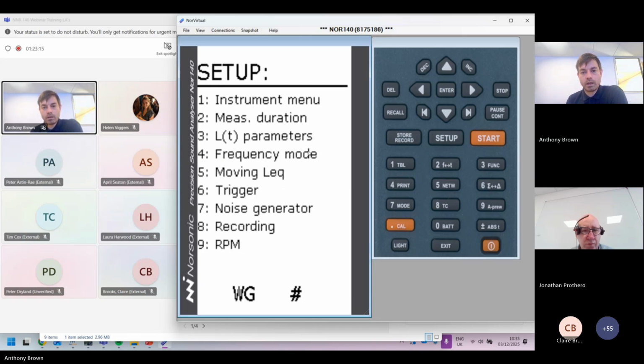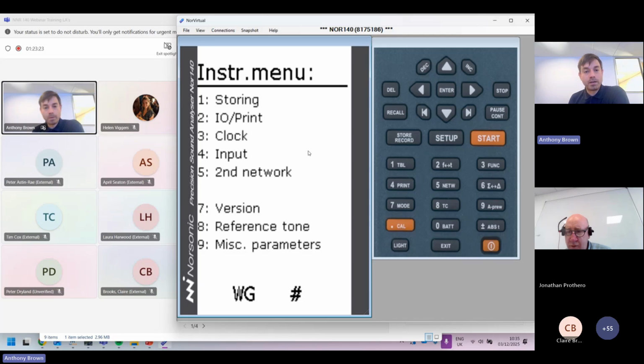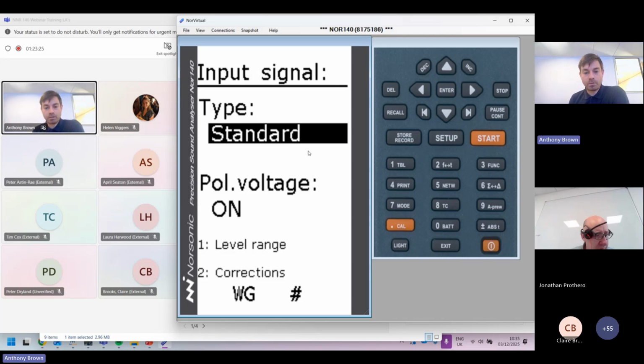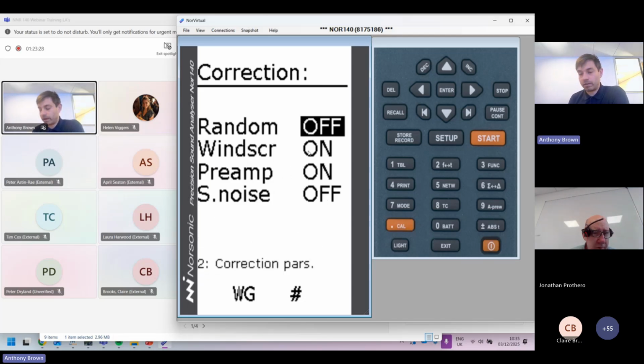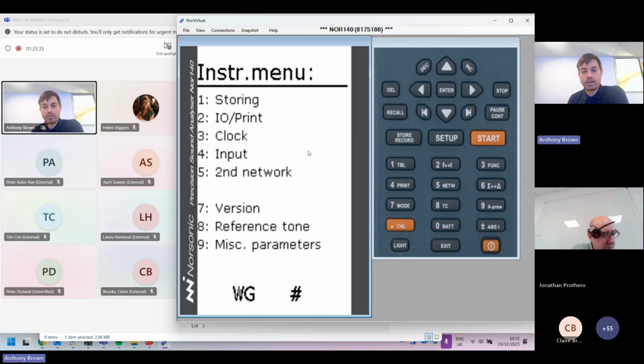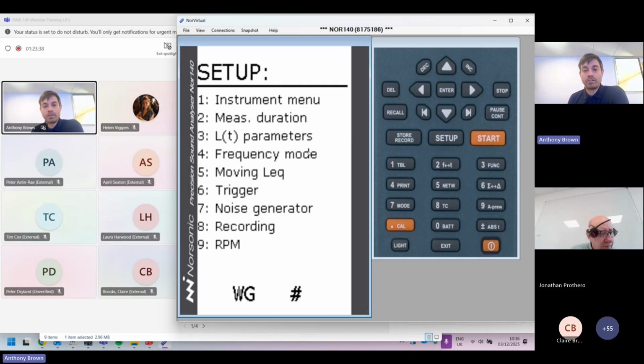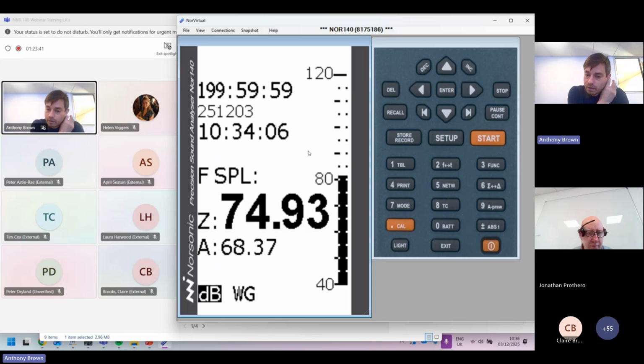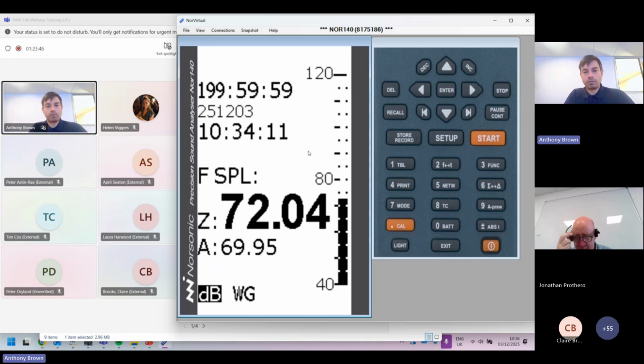So it's the enter key to go all the way back. If you are still a little bit unsure where you were with that, it's the instrument menu number 1, the input menu number 4, pressing button number 2 at the bottom for corrections, and then changing windscreen on or off by using the inc or dec key, and then press the enter key to go back, and keep pressing the enter key until you're all the way back. This is actually in the user guides in the PDF. So if you haven't managed to do that, got stuck with it, don't worry. Just have a look at the PDF guide. I've print screened every step of what to press.